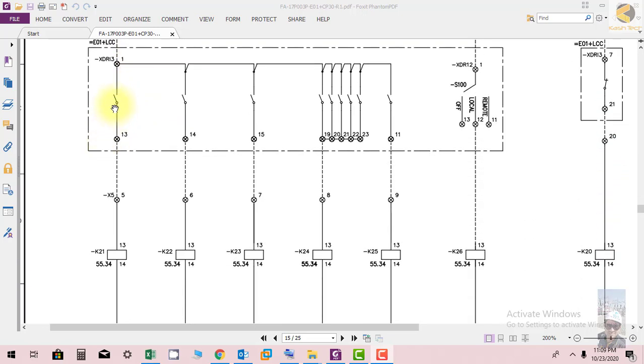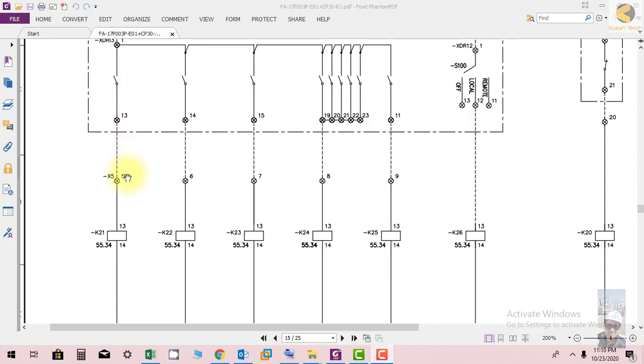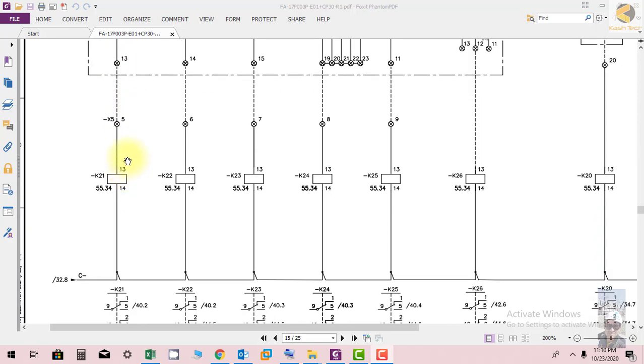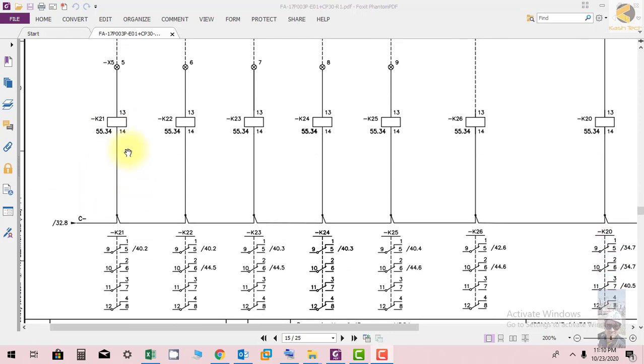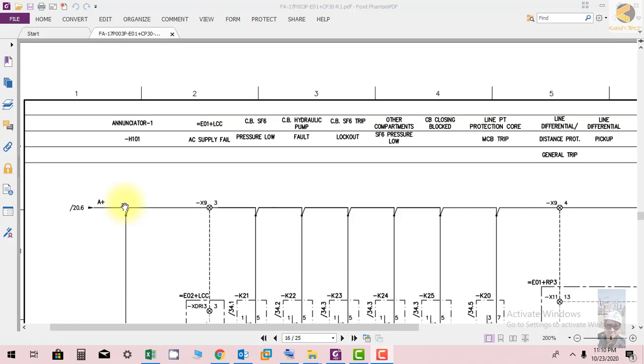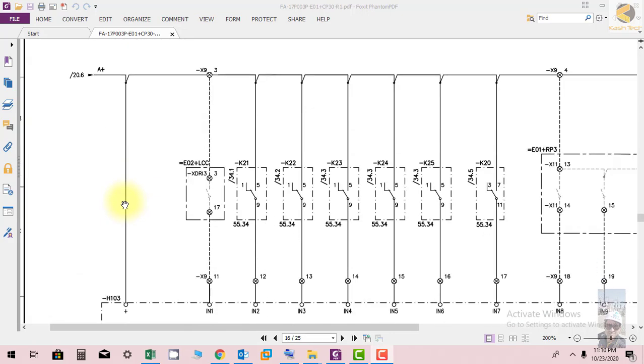If pressure is low, the contact at the LCC local control will close, and then K21 will pick up. When K21 picks up, we go to sheet number 40.2.